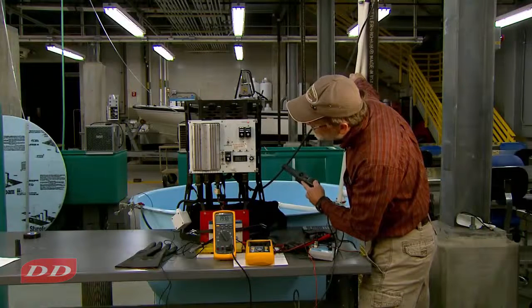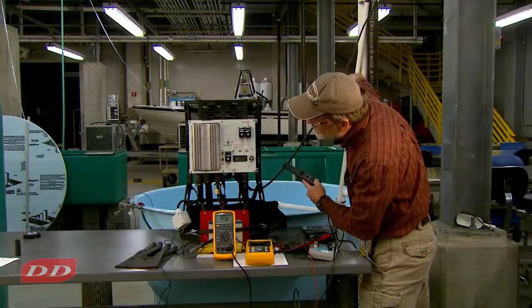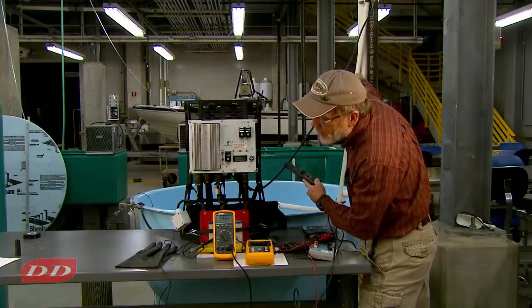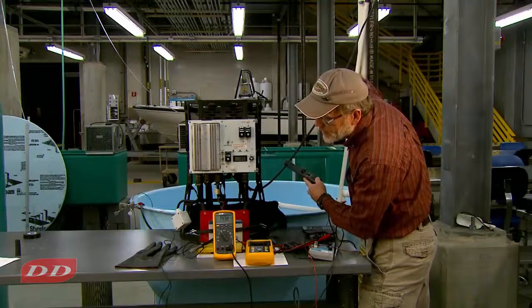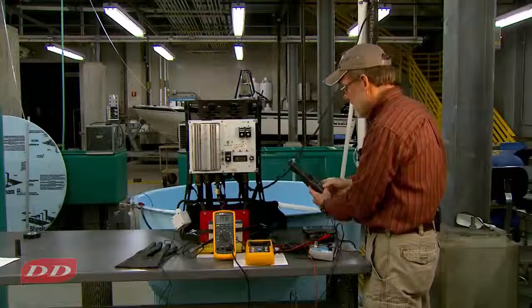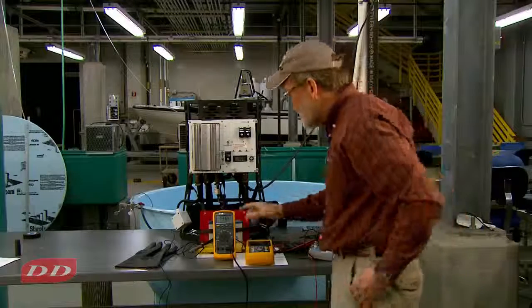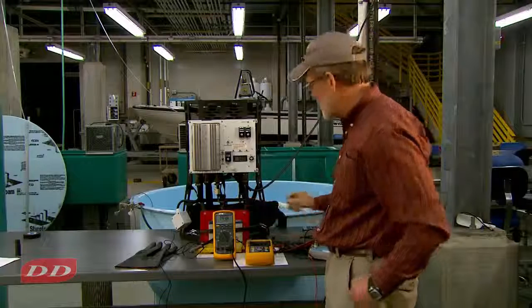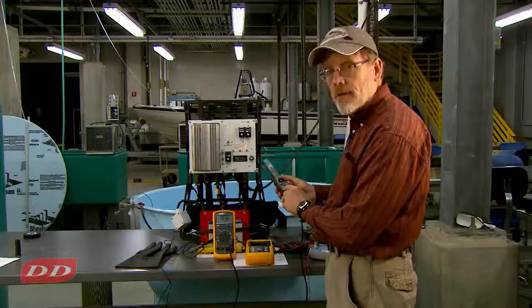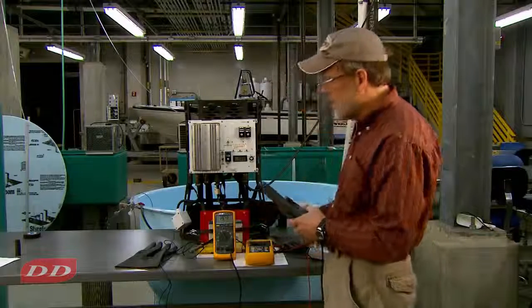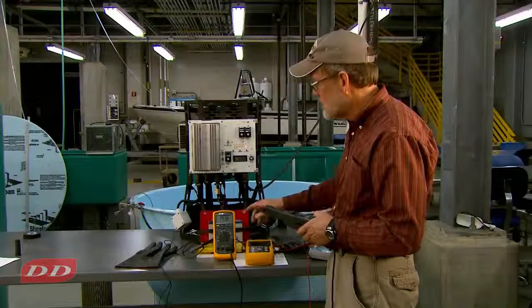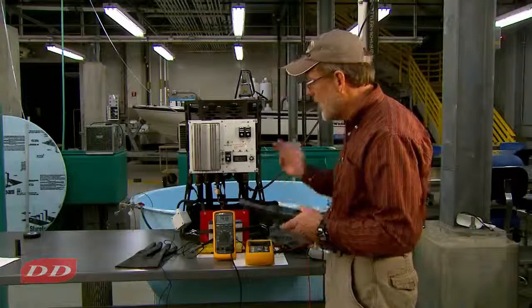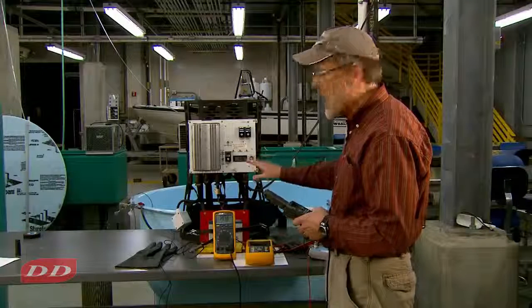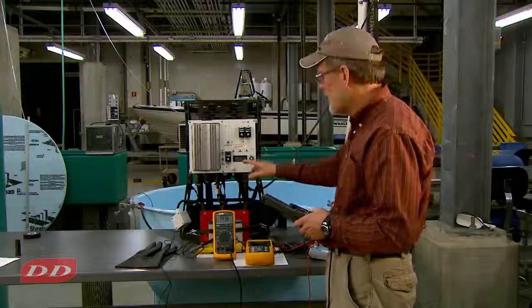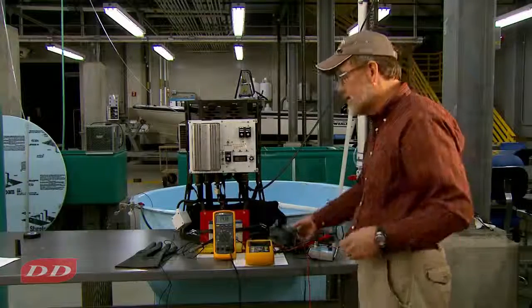Okay, so the ammeter on the backpack unit says 1.80 amps, and on the multimeter we have 193.8 millivolts. So now again, this is the millivolt level. To get to amperage, we need to use the scale, which was 100 millivolts per amp. So we divide that 193.8 by 100 millivolts. That gives us an amp reading of 1.93, 1.94. That was fairly close to the reading we had, again, on the ammeter. So that is the correspondence.